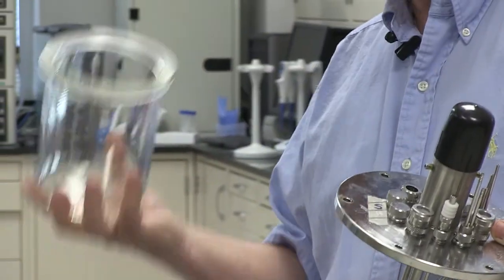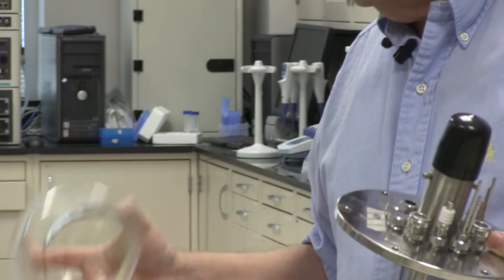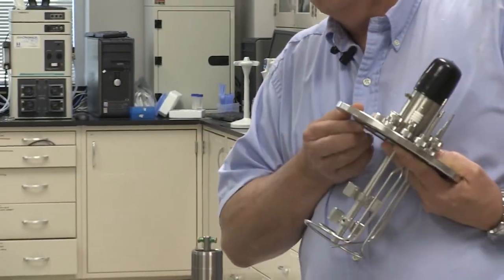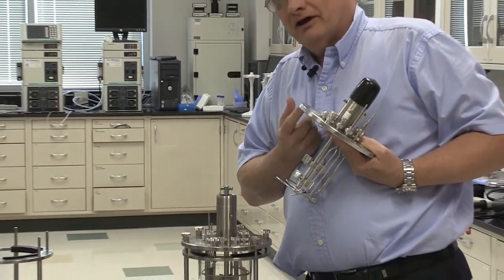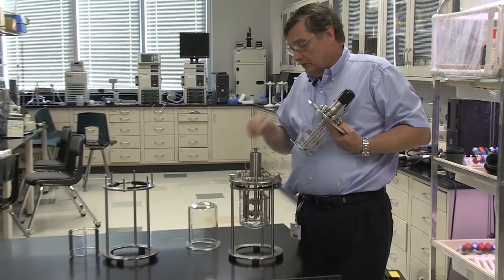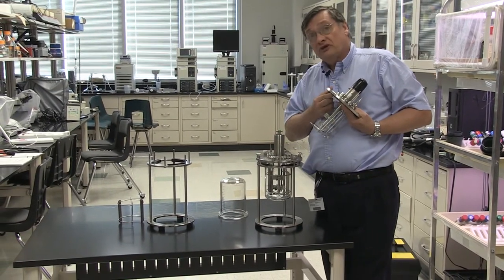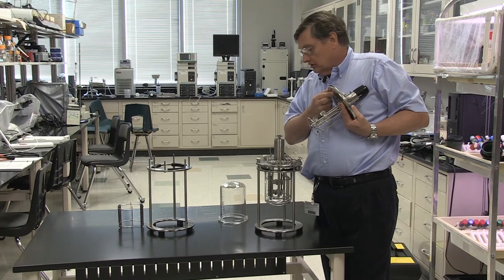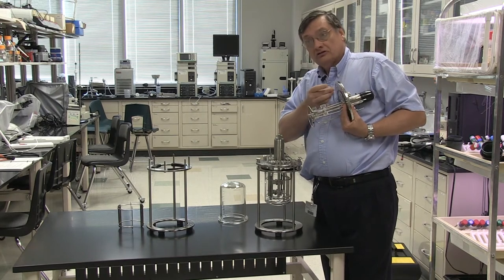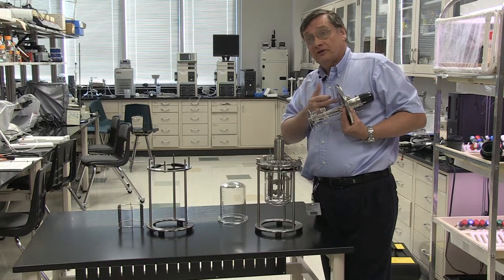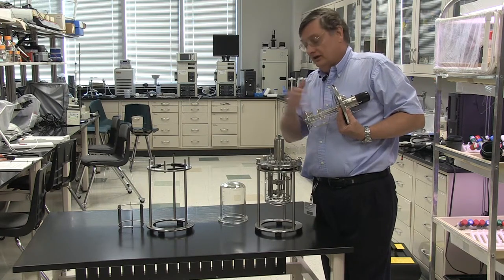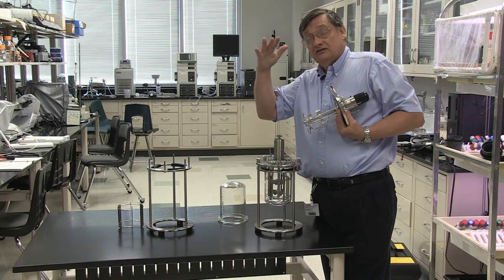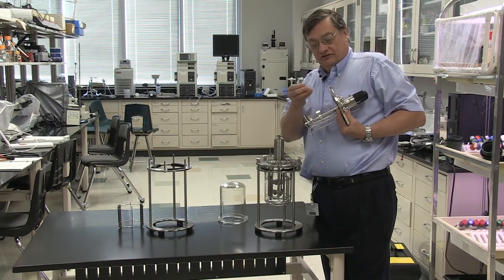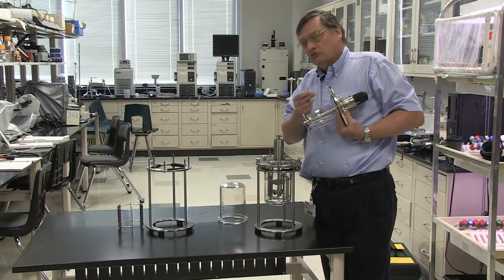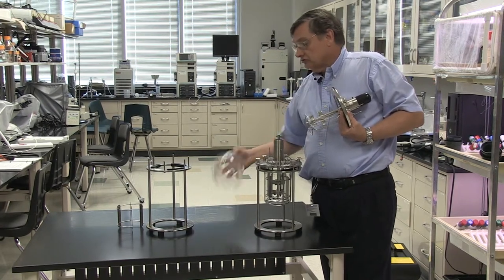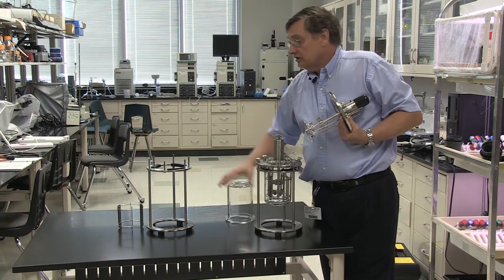Now that's important for a couple reasons. One, it obviously seals the vessel to prevent leakage. The other thing, it provides a cushion between the glass and the metal. It's really important that in all these connections there's always a piece of rubber or some material between the glass and the metal, because the glass and the metal have different thermal expansion coefficients. And these go in the autoclave, and they get heated and then cooled. So if it's metal on glass, glass almost always loses. And so you could wind up cracking the vessel.